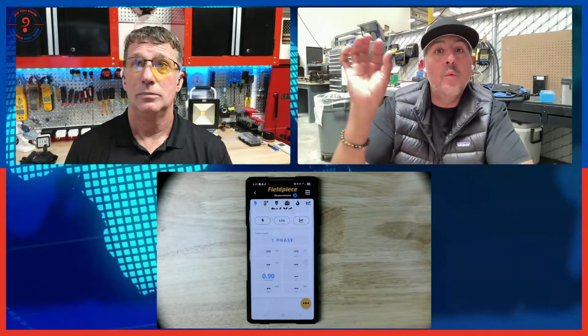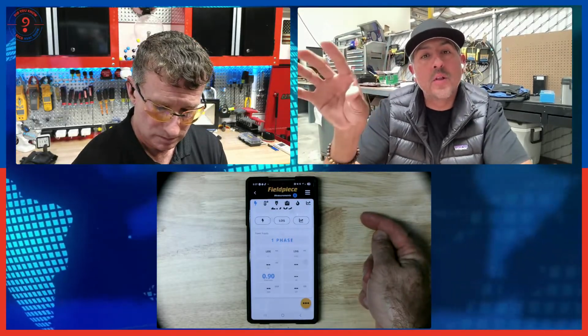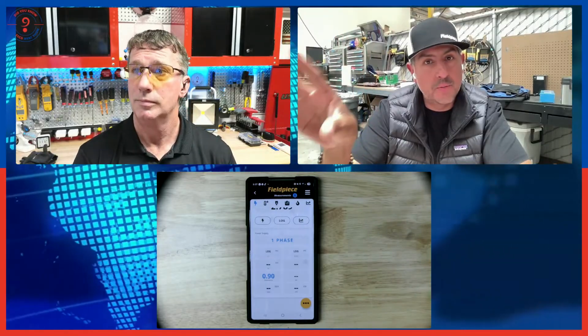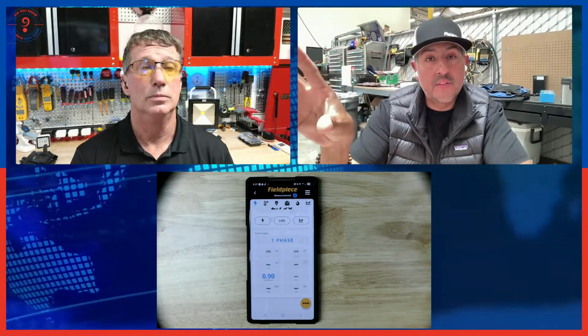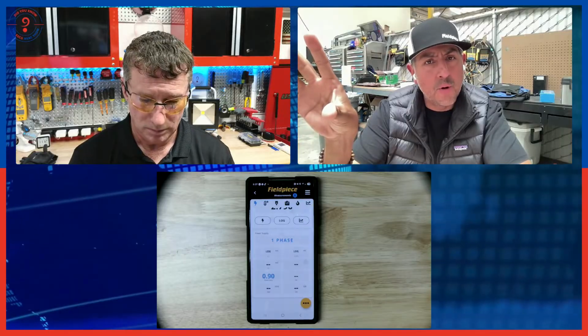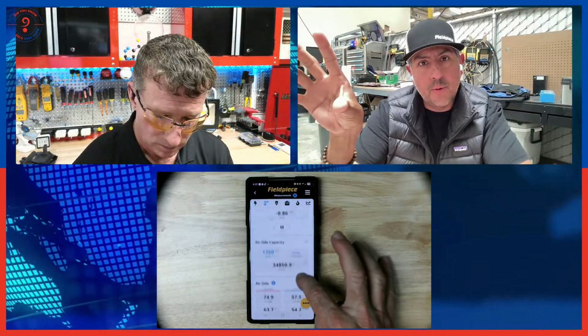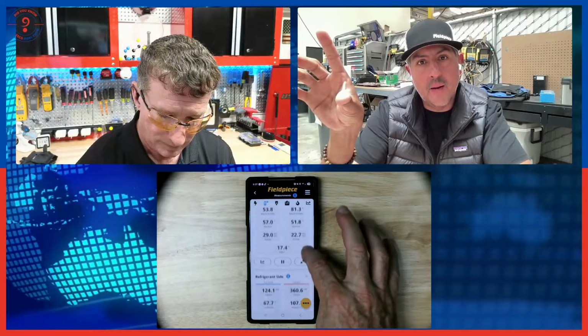Okay, so now we're monitoring the airflow, the refrigerant charge. We saw superheat, subcooling, we saw delta T. If we look at the static pressures, we saw you were approaching 1 on the static pressure side, at the very top of the screen.